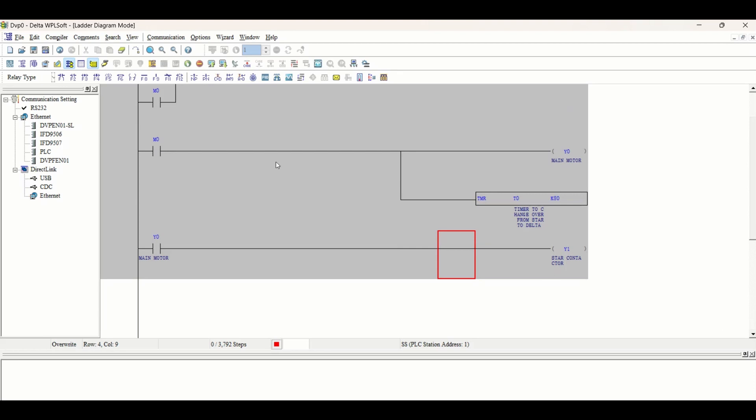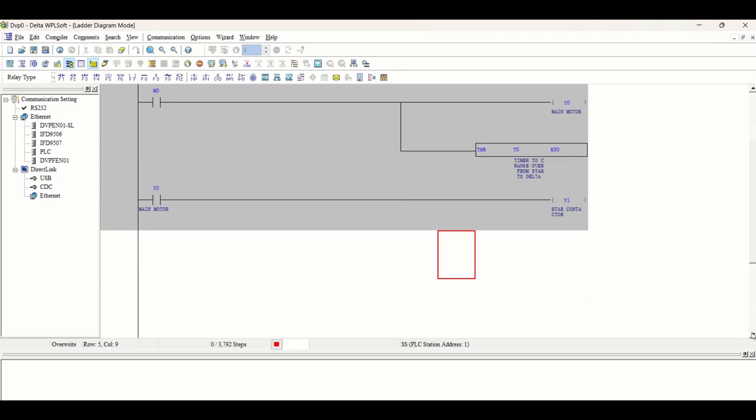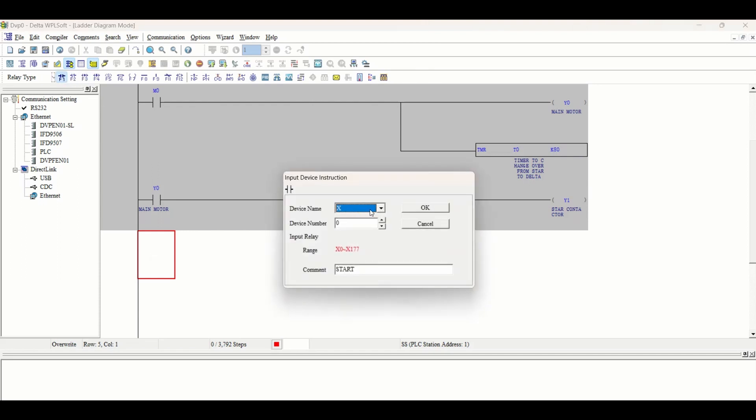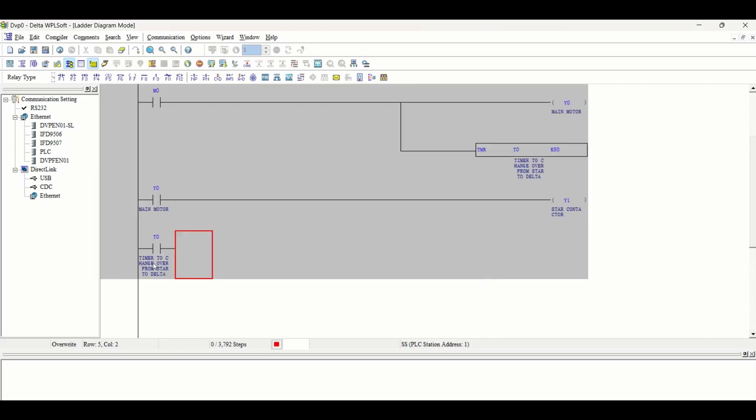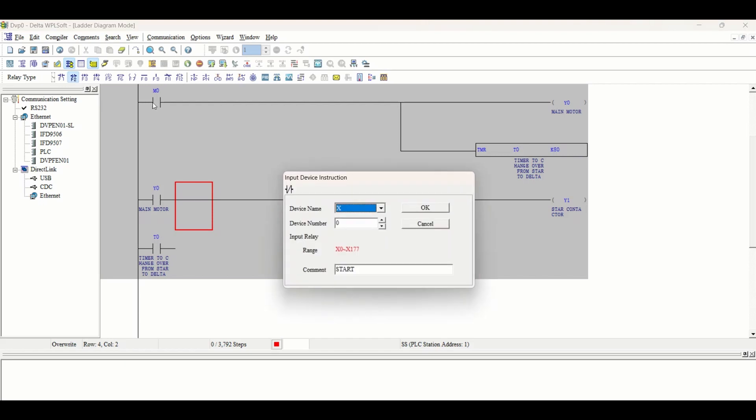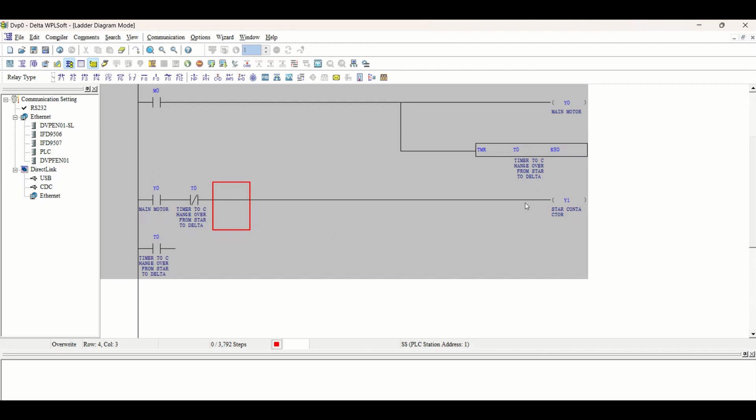After pushing the start push button, main motor and timer will start, and the main motor will start with star contactor. After a while, when 8 seconds is complete and motor is at full speed, T0 will go high and stop the star contactor using an NC contact.